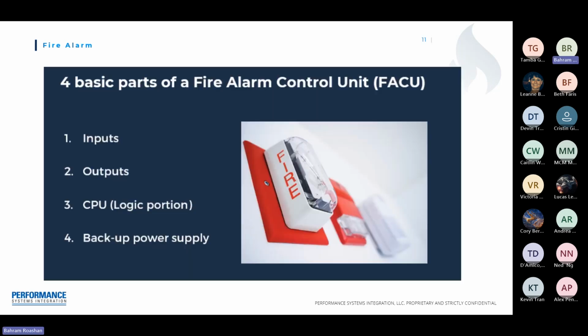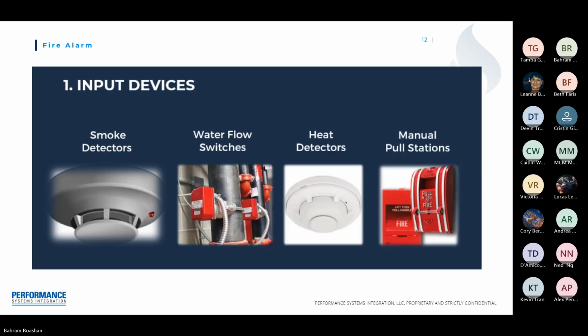I'm just going to go over how the fire alarm system operates. Our 4 basic parts of a fire alarm control unit are our inputs, our outputs, the CPU, which is our main logic board, the brain, and the backup power supply. Input devices: smoke detectors with thermal detection technology meet the latest NFPA 72 code requirements. Once they detect smoke, they send a signal back to the fire alarm control panel, setting off the output, such as a horn strobe, and then sending a signal to the central monitoring station for fire department response.